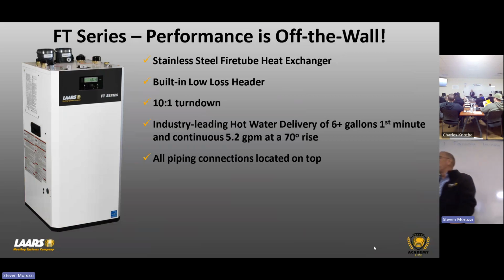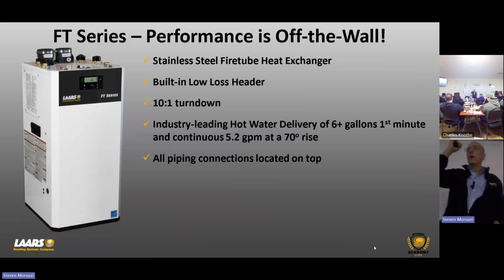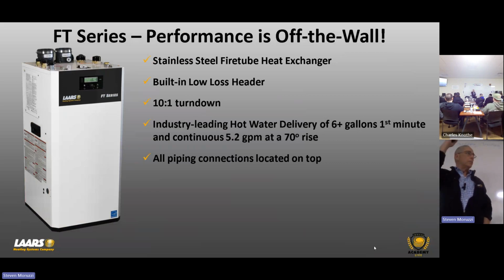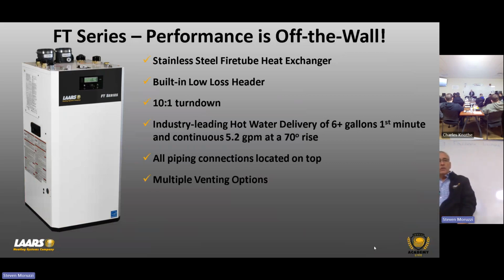A lot of your wall hungs, what do you do with that space underneath them, right? You're creating a primary, secondary manifold. What are you doing with it? There's nothing else under there, right? So again, on the floor boiler, everything's right off the top. Here in the US, in most cases, we're in a basement, we're going up. If you take a wall hung and you mount it, you get primary, secondary, where's your piping going? Straight back up, okay? So everything's right off the top with venting, gas, electric, etc.